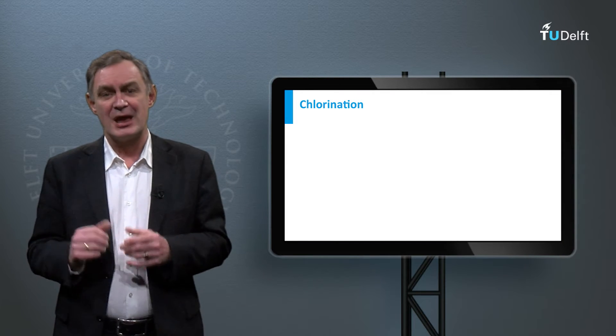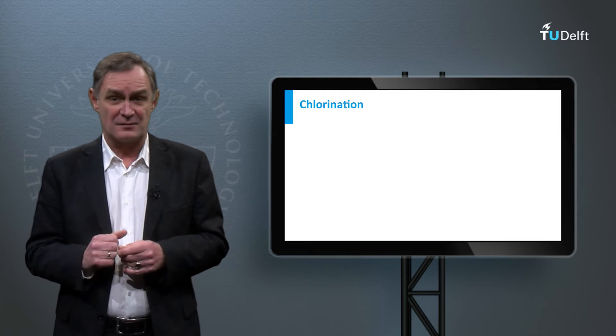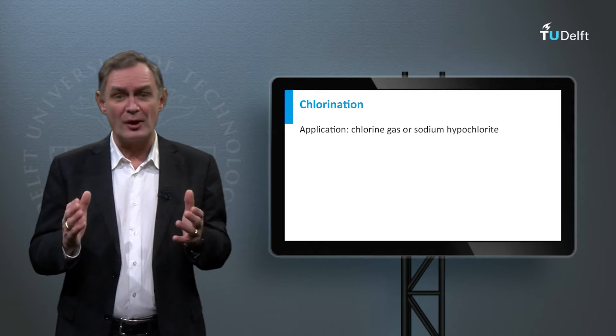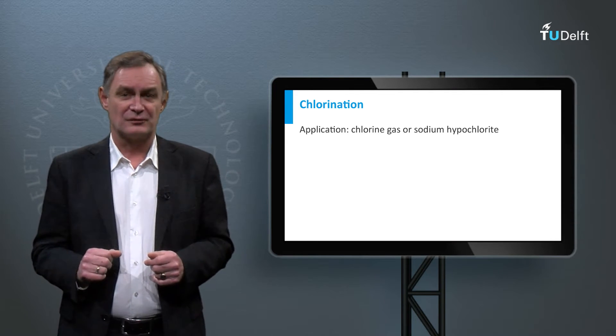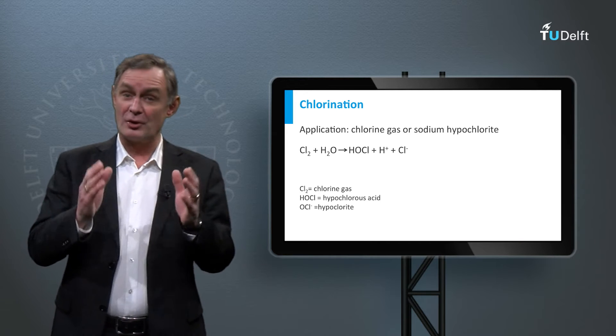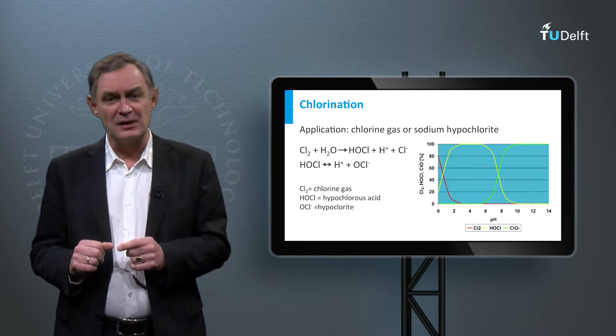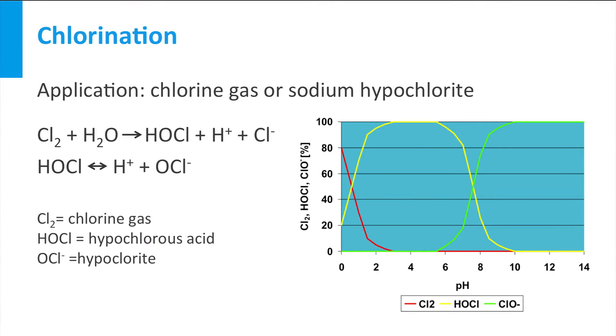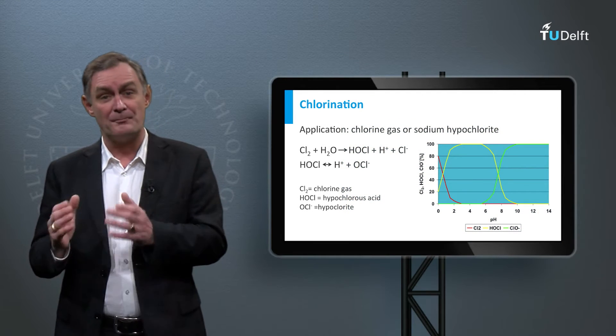Chlorine is the most widely used disinfectant, since it is the easiest to operate and the least expensive disinfection technique. It is applied as chlorine gas or as sodium hypochlorite liquid or powder. When chlorine gas is used, it dissolves in water and hypochlorous acid is produced. Depending on the pH, hypochlorous acid is dissociated into hypochlorite. In this figure you can see the distribution of chlorine gas, hypochlorous acid, and hypochlorite for different pH values.